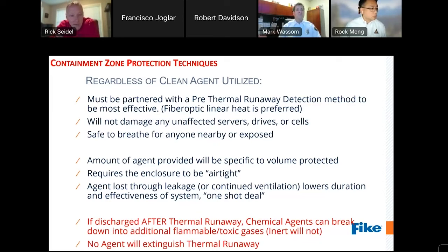The amount of agent provided will be specific to the volume being protected. One of the disadvantages to clean agents is it does require the enclosure to be mostly airtight or have a high degree of room integrity, because agent loss through leakage, or the other variable to keep in mind, continued ventilation, will lower the duration and effectiveness of the system, as most of those systems are one-shot deals. And once that cylinder is empty and the room is flooded, there's no reserve supply unless it's designed as such.